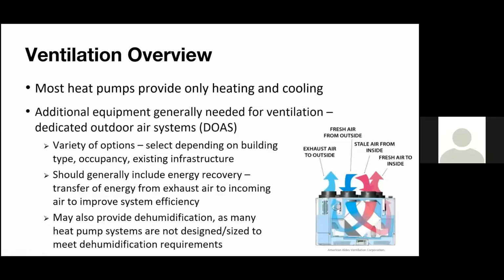So a little bit more on ventilation. Most heat pumps provide cooling and heating, right? So they're not really focused on fresh air too much, and typically you'd want to have some kind of dehumidification, because we're controlling to sensible temperature, and we're not controlling to latent, which is the moisture in the air. So you want some kind of ventilation system that can deal with that. Your first option, which I don't typically recommend, is you can bring raw outside air and try to dump it into a space. First off, that's not going to be comfortable. And that's also going to increase your heat pumps, your HVAC equipment, by a ton. You're adding a lot of first costs because you don't have something to really treat that air.